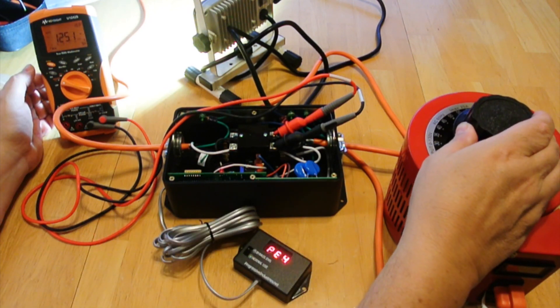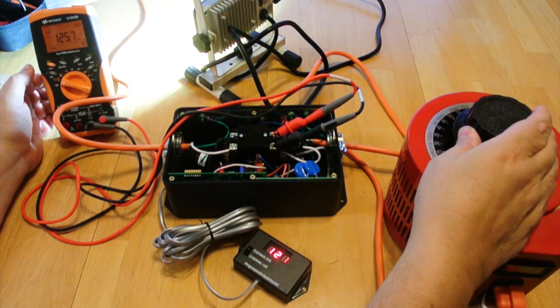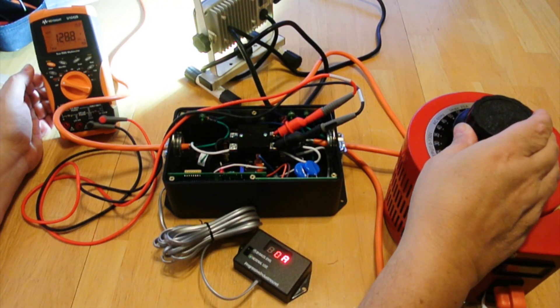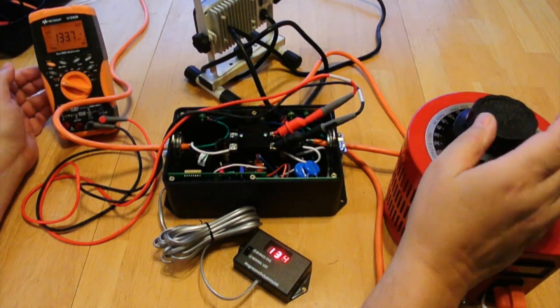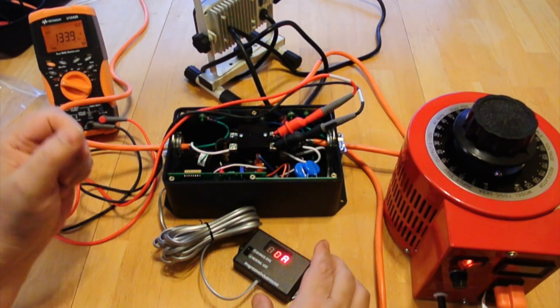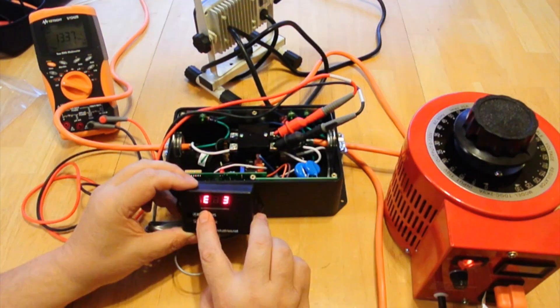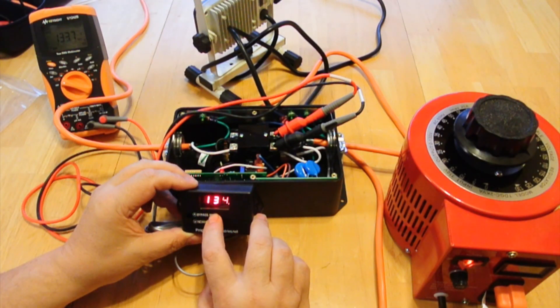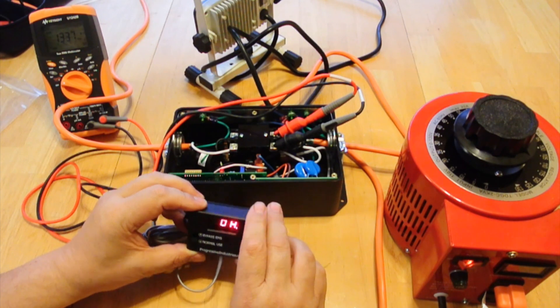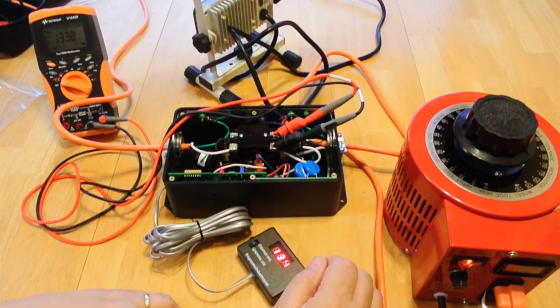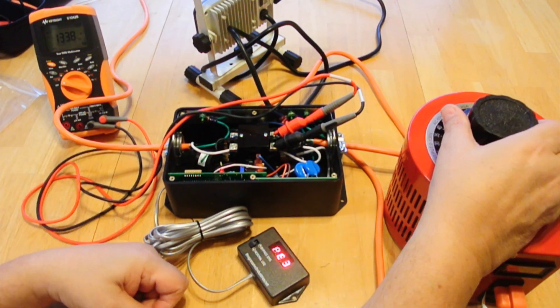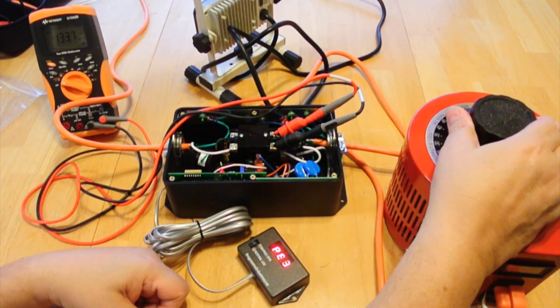We're going to bring this up to more than 132 volts, and again it shuts off. You see now we have E3, so that's error 3. Now when we bring this back to less than 132 volts, there's a 15 second delay before this will turn back on.